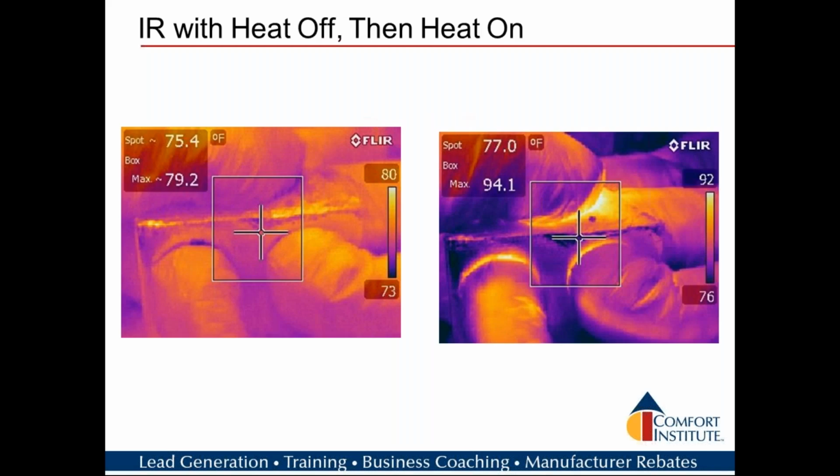Here's another shot with the infrared. We're showing it with the furnace off, and to the right of here, we're showing it with the furnace on. Again, we're able to demonstrate the fact that we have duct leakage. We are in the duct business. It's part of what we should do. We should become duct experts within our industry. This is one of the ways that we can show homeowners what's happening in their homes and solve a lot of problems.